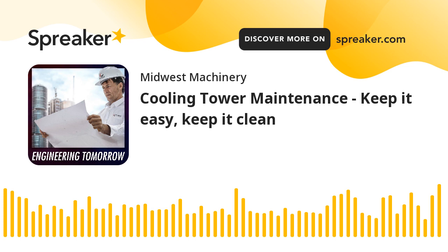The other thing I wanted to quickly touch on is water treatment and a couple of different options. I know you mentioned chemical treatment. I've heard some stories of big chemical treatment companies where, when they come to check your system, they don't even look at the tower. What they're doing is checking the most convenient spot for residual biocides. So your tower could be filled with gunk, it could be scaled up, but if it's a 100-degree day, they're not going to go out on the roof and do a thorough inspection of your cooling tower.